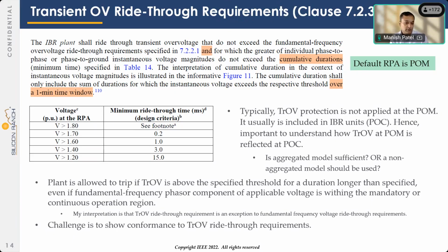You could have an RMS voltage at 1.05, but for a very short duration over one cycle, the voltage went up to 1.72. Your RMS voltage does not change a whole lot because for the rest of that full cycle, the voltage was back to normal. So if the voltage went above 1.7 for more than 0.2 millisecond, then even though the voltage remained within the continuous operation region or mandatory operation region, the plant is allowed to trip, right? I don't think many people get this, but it's an interpretation that the transient voltage ride-through requirement is actually an exception to the fundamental frequency voltage ride-through requirement.